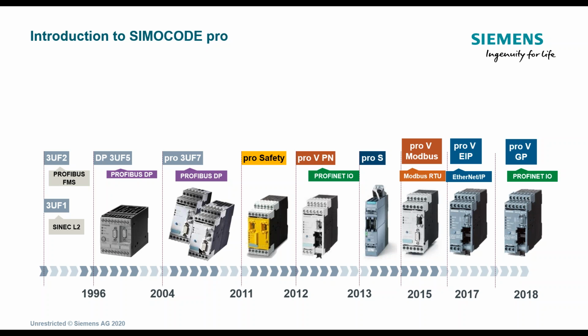And frankly, with the SIMOCODE, there are some digital outputs that eventually over time will fail, and you'll need to replace the SIMOCODE. So instead of unwiring all of your motor leads, your T leads, and going to the field to pull out the CT when it's integrated, all you have to do is undo the cable at the bottom, and these terminal blocks are removable. You don't have to unwire anything. Remove it from the DIN rail, put in the new unit, plug in the terminal blocks, plug in the CT cable, and then download the software to it, the PLC or the logic that's in it, and you're up and running. We'll talk a little further about that in just a few minutes.